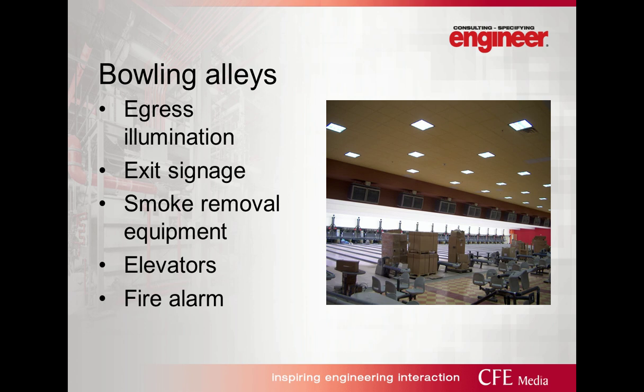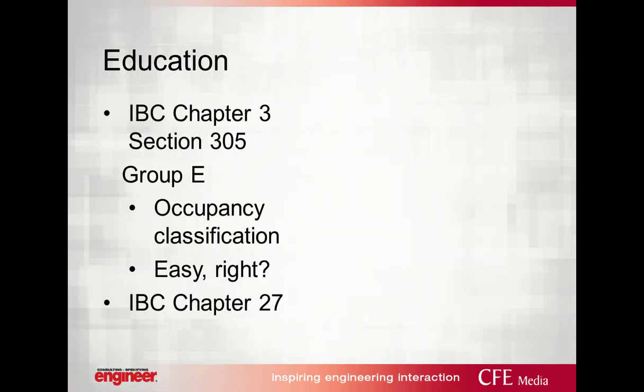I obviously don't exit them across the bowling lane, so that's not of major concern. But a bowling alley also needs to be considered, especially when it's applied for the application you're dealing with. How do I get those people out of that building safely? Where is my exit signage going? Is it visible? Is there elevators? Is there a fire rescue elevator planned for this space? Typically not for this type of application, but maybe. A fire alarm? Usually a fire alarm system is involved in this.